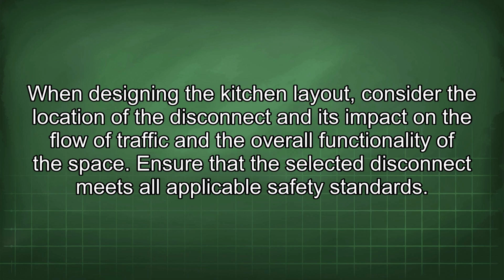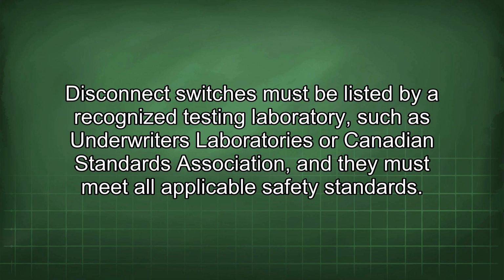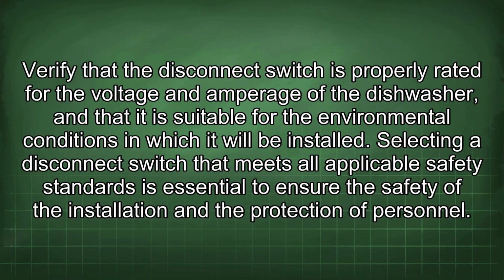Ensure that the selected disconnect meets all applicable safety standards. Disconnect switches must be listed by a recognized testing laboratory such as Underwriters Laboratories or Canadian Standards Association, and they must meet all applicable safety standards. Verify that the disconnect switch is properly rated for the voltage and amperage of the dishwasher, and that it is suitable for the environmental conditions in which it will be installed. Selecting a disconnect switch that meets all applicable safety standards is essential to ensure the safety of the installation and the protection of personnel.